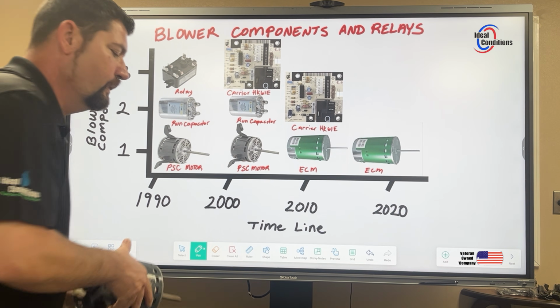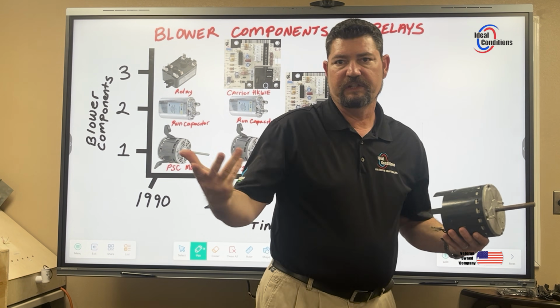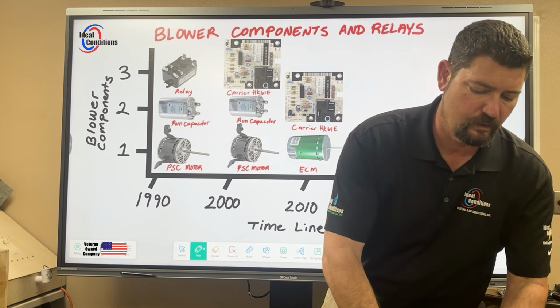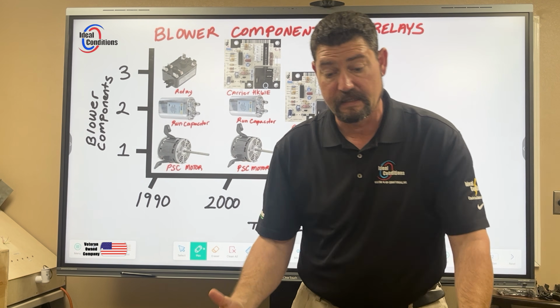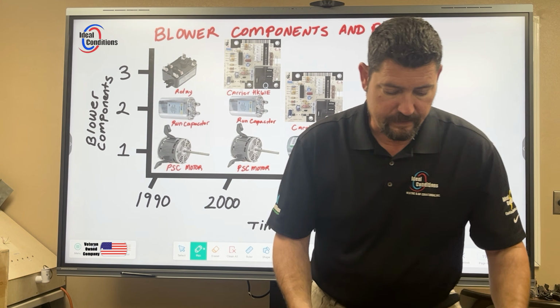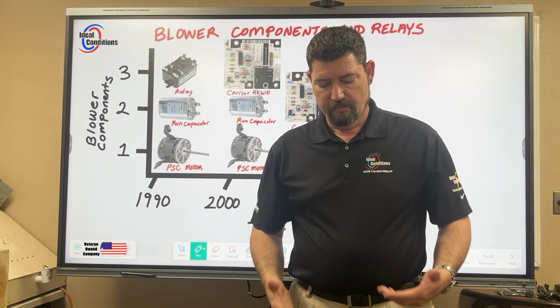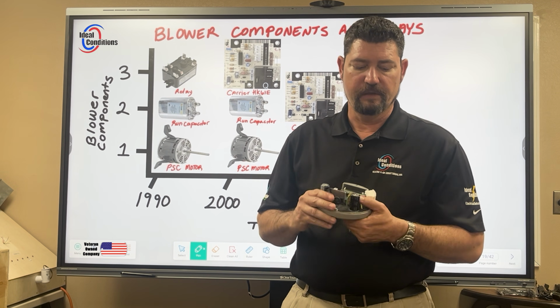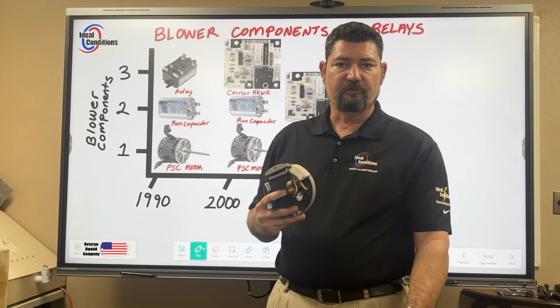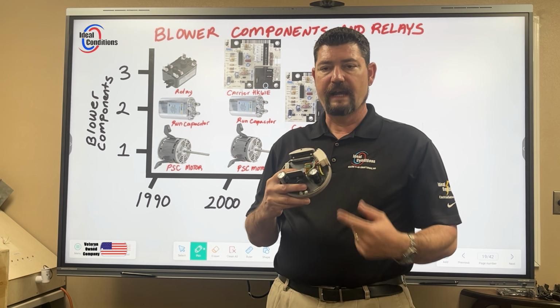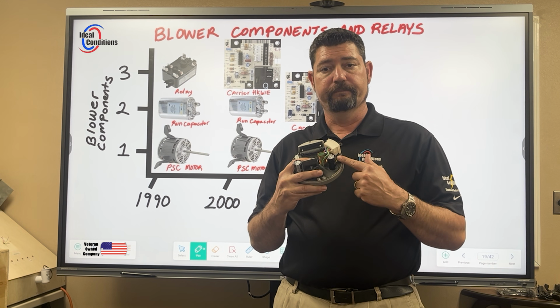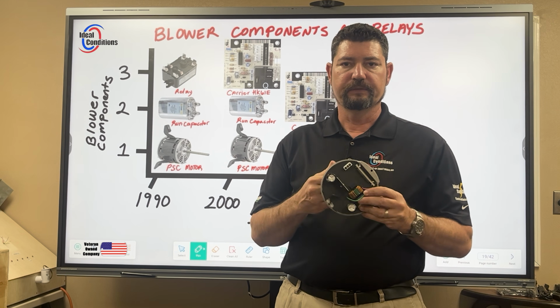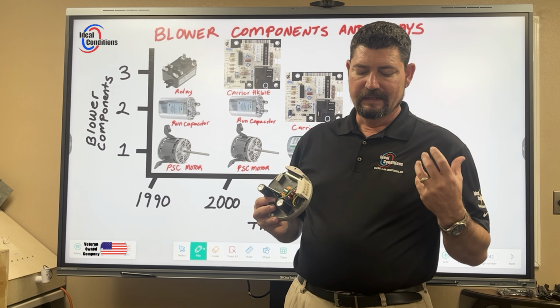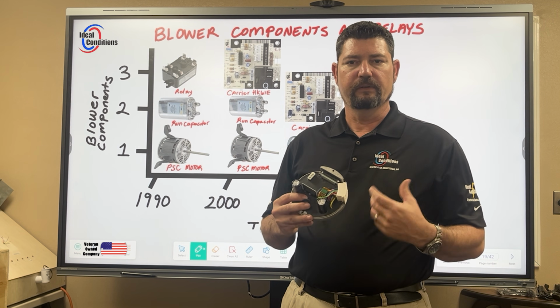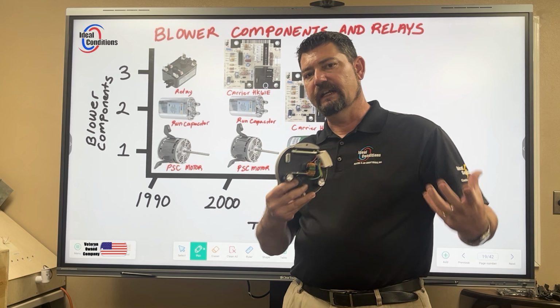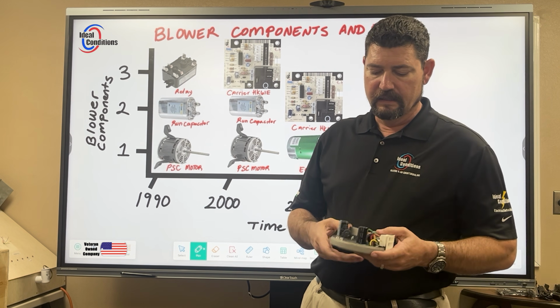Okay, and so whether it's in or out, if you want to test it out of the box, if your customer wants to know, or if you're DIY, you want to say, hey, did I get another bad motor out of the box, there's ways to test it, but you have to pull this off. And the reason why is because I'm actually breaking one of those windings across a relay, okay? And that relay is built into here. And so if I'm leaving everything plugged in, I'm not gonna be able to do it the same. I'm gonna have to take the module and disconnect it from that motor to test that out.